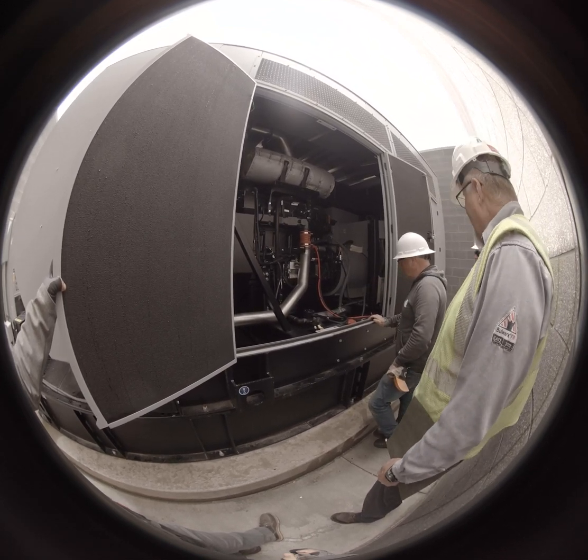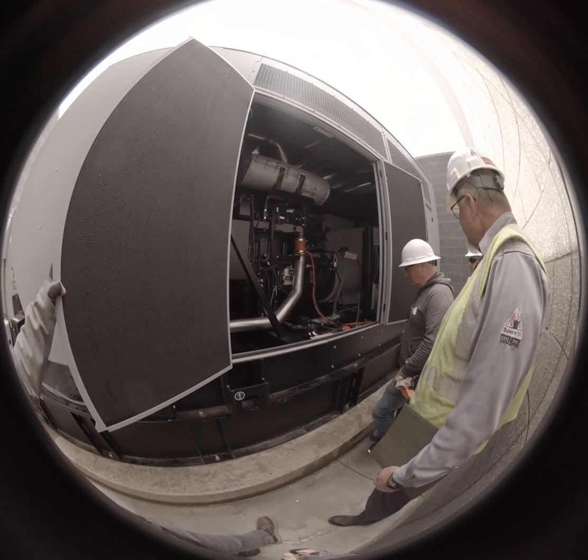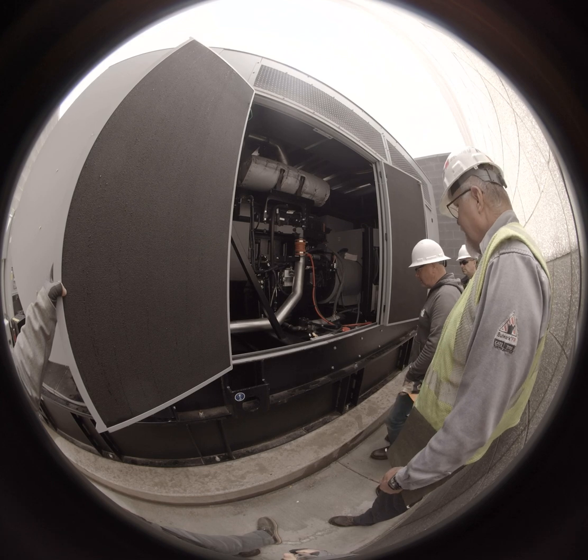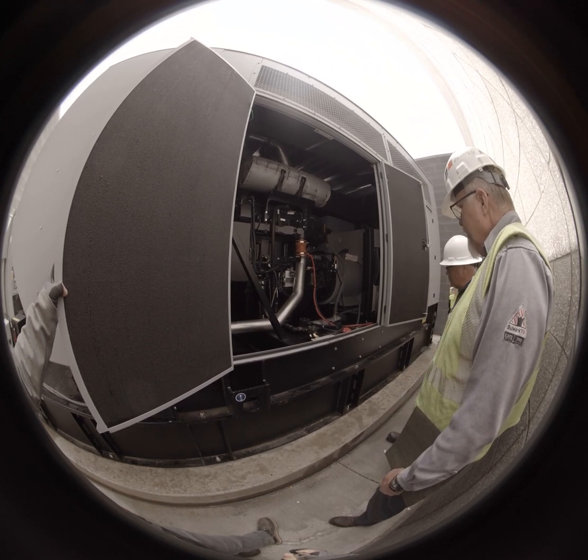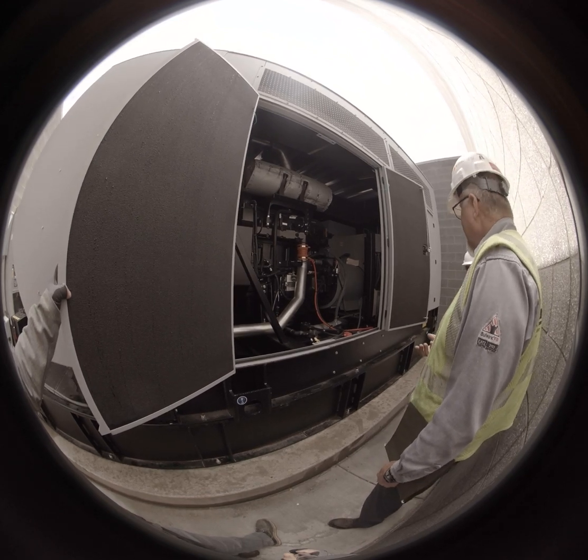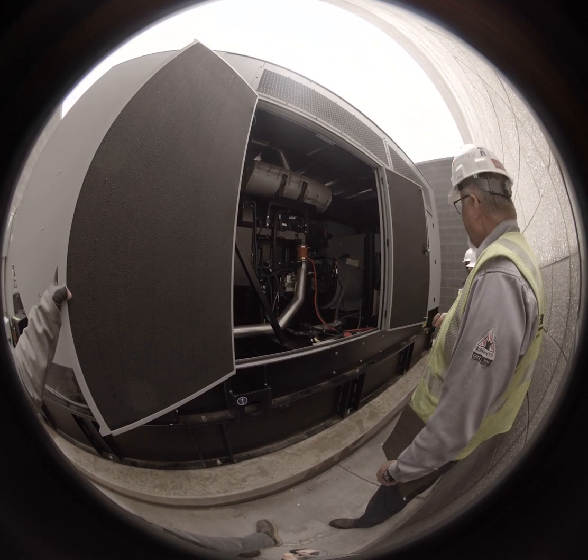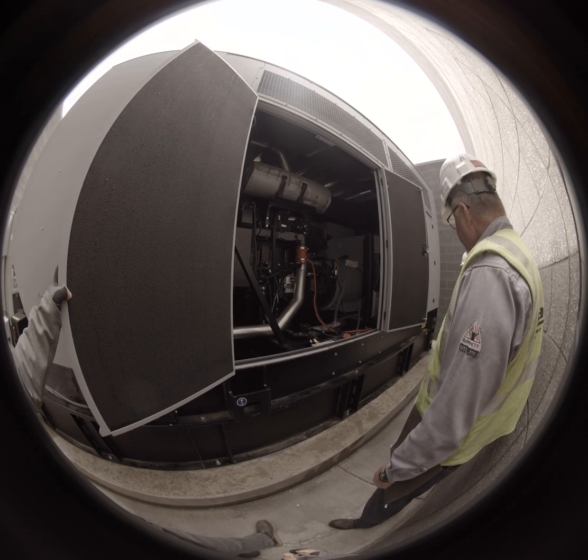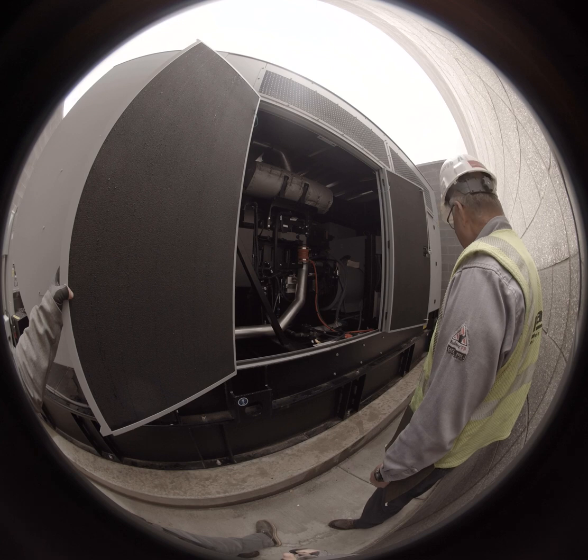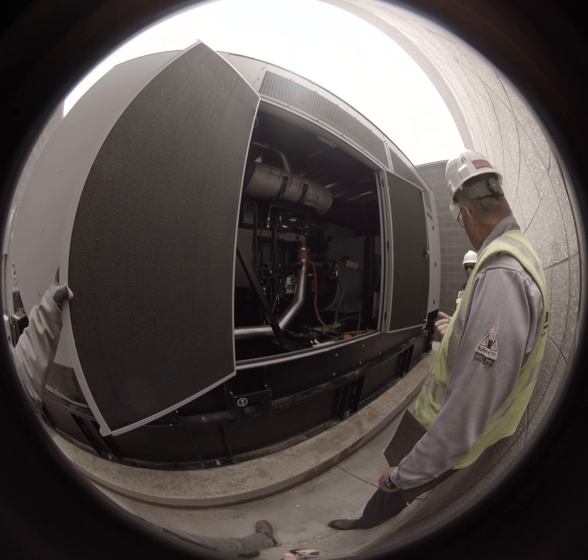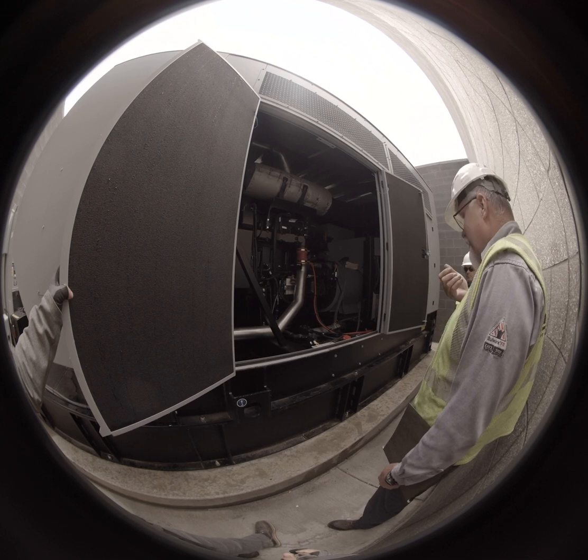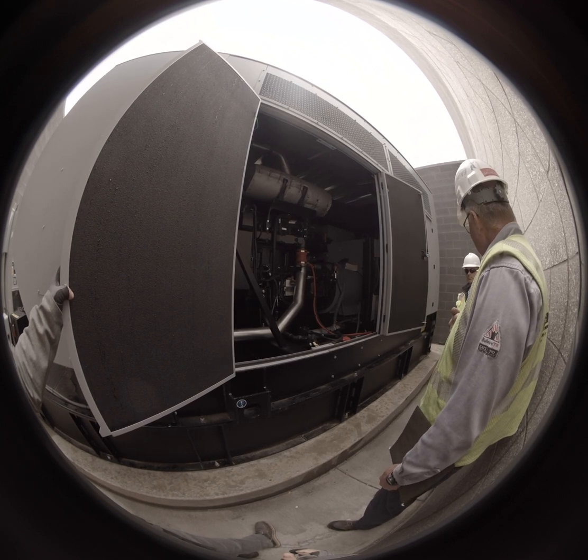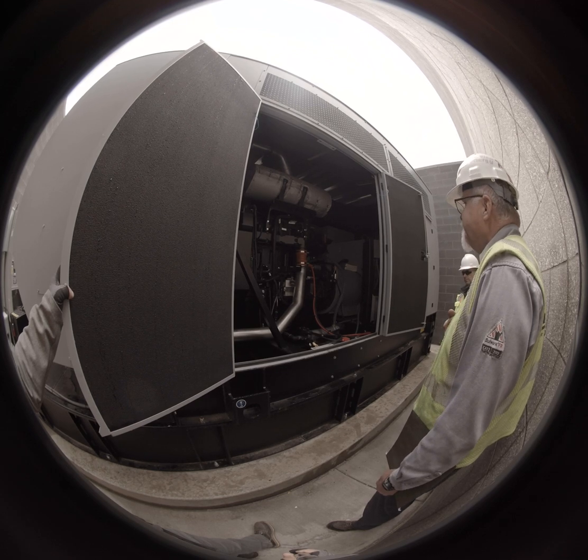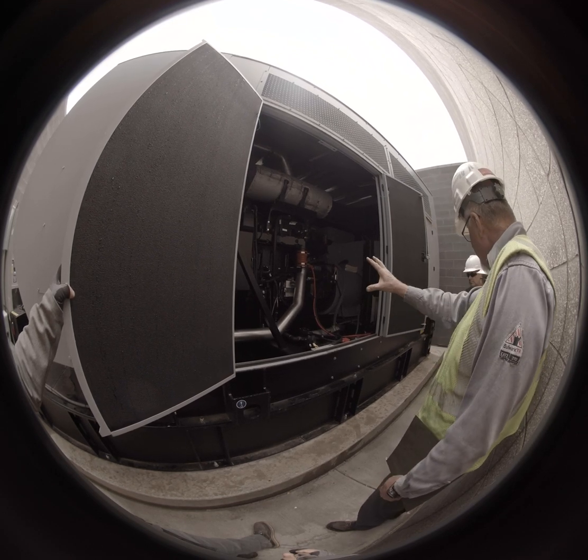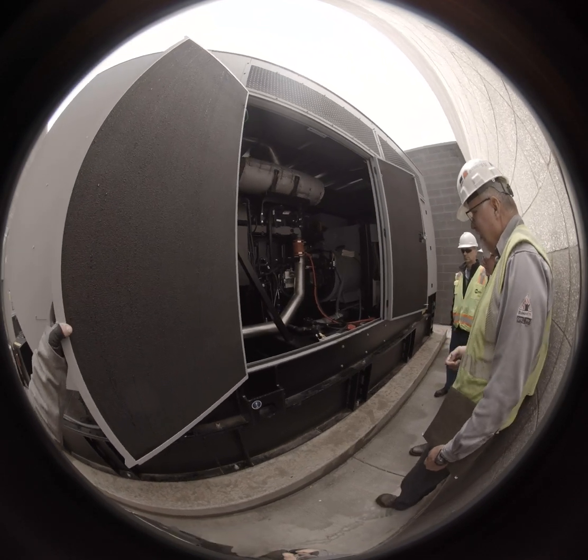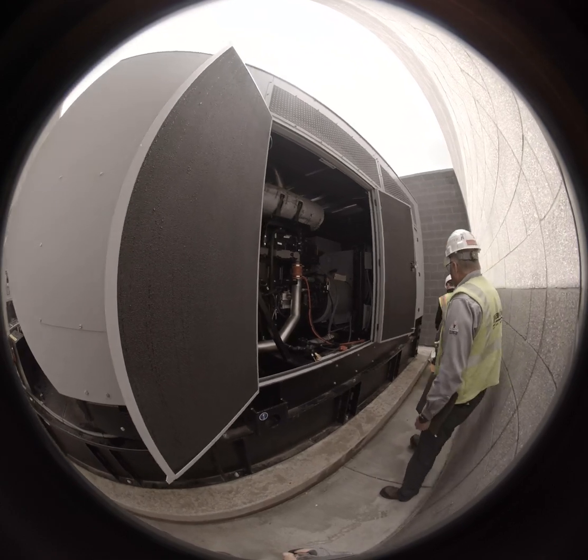Right here in front of you, we have two Group 31 batteries. These are maintenance-free style batteries, so there are no water levels to check or anything of that nature. The batteries, typically, according to NFPA code, should be replaced every 30 months. They don't say you have to, they just recommend it. And my saying that I always say is, without batteries, you have a very nice thing holding the slab down, because that's all it's good for if it doesn't start. So, okay. Any questions on this? Okay, let's move to the next door here.